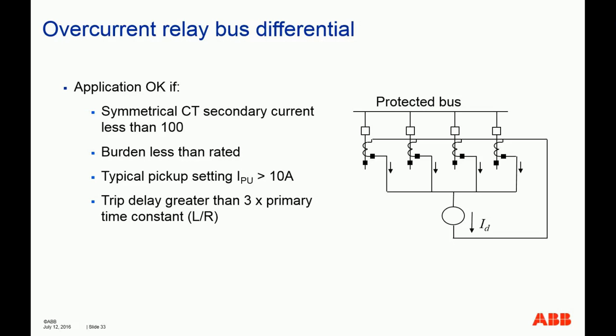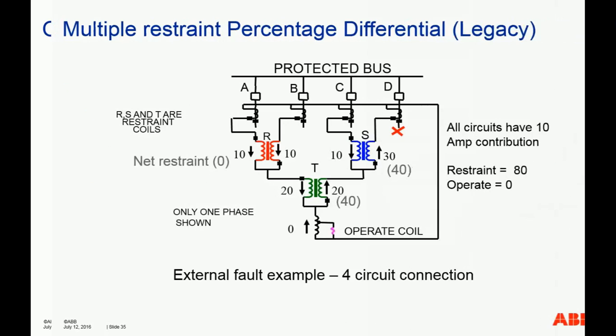Okay. And as you can see, that's the reason you need to set the pickup quite high, to ride through the measurement error. That's why it's not going to be very sensitive. Okay, so the typical pickup is greater than 10 A secondary.